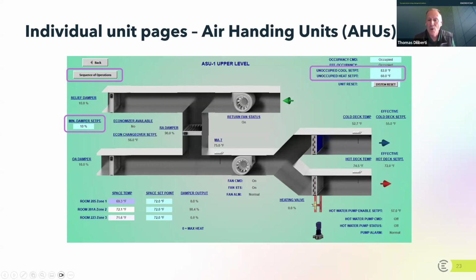This is a very common programming decision that people make is they set their dampers in a minimum position. And so 10% is very common. It's certainly not wrong, but I want you to be understanding what that means. It means no matter what's happening in the building, as soon as this system turns on, this damper is going to 10%. And if there's no occupants in the building or very few occupants, it means that you're heating or cooling air that you don't have to because you're in some type of minimum position. And so this minimum damper position, again, is something that some organizations want because they're concerned about ventilation. They set it at 25% or they'll set it at 30%. This has the potential for being a big energy waste again. And so you want to understand how this is set, what the rationale is, and the logic, both programming logic as well as the people that are making these decisions in order to make sure that your systems are set in an efficient way.